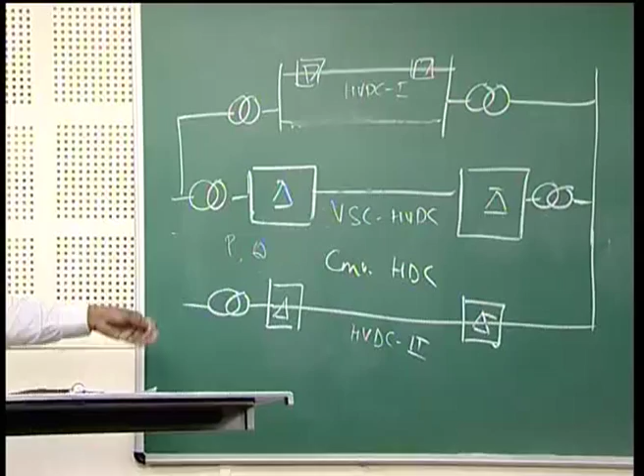Unlike AC cables, which generally have a technical limit of around 100 kilometers due to reactive power charging and the losses, which we cannot exceed, even though earlier it was not more than 50 kilometers. Now, with the help of various insulating materials and advances in those technologies, people claim they can construct AC cables of approximately 100 kilometers. And we cannot go beyond this, because if you go beyond it, then even though at your receiving end you are not taking a single ampere of current or power, your sending end current is the full load rating of this cable, and if you exceed the receiving end power, this cable will puncture and burst, and also there are huge losses. So, the DC cables have no such limits, we can go up to the thermal limit.